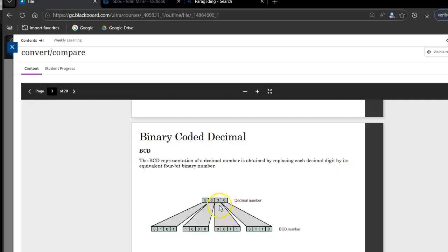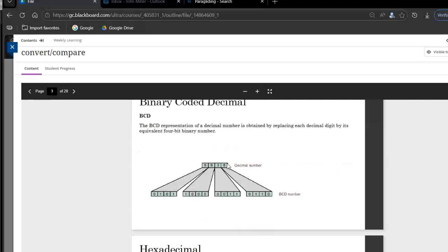So they would key in 340, and the machine would run until it counted that many parts, and then it would shut off and put up a finish light or something like that. So binary coded decimal is one way. A lot of thumb wheels have them, and a lot of displays used to use them. Now it's a lot easier to just use an HMI, but you will come across these.